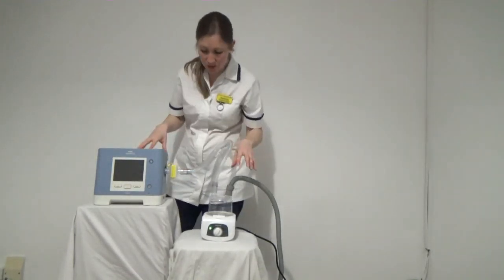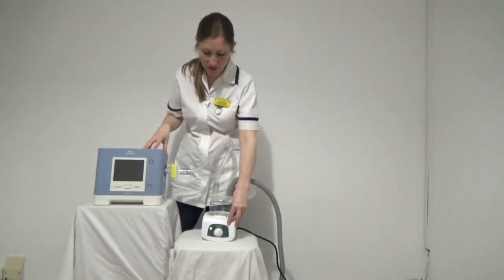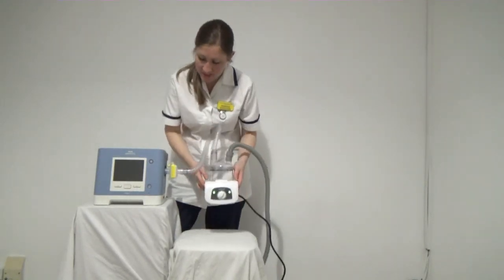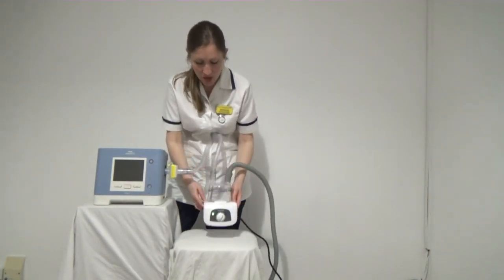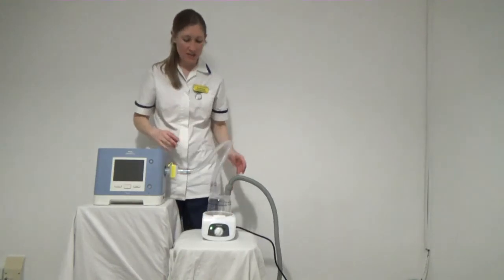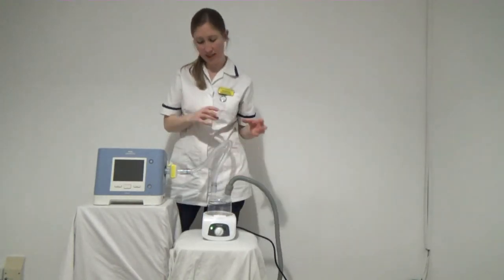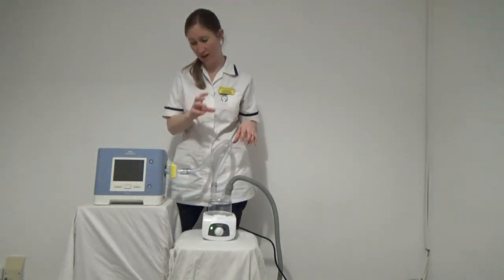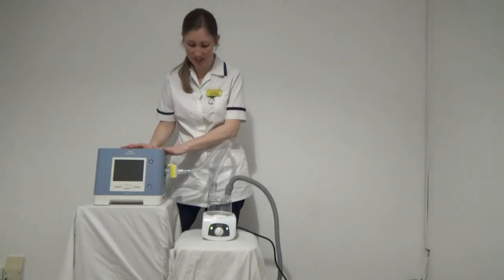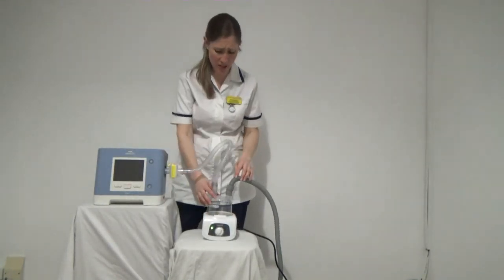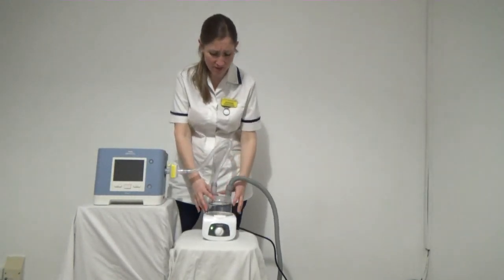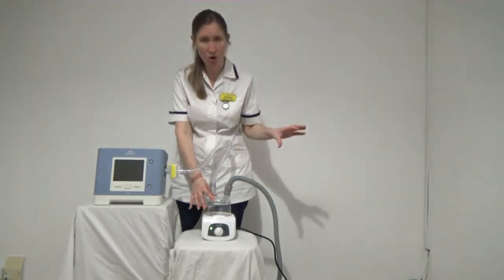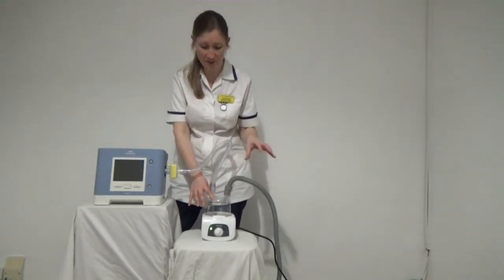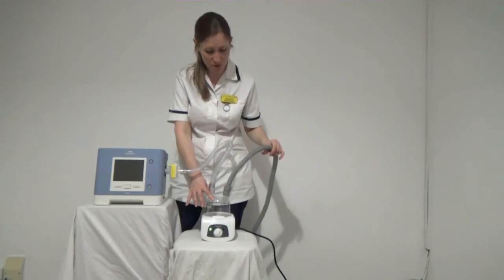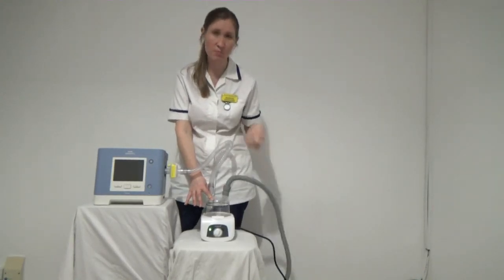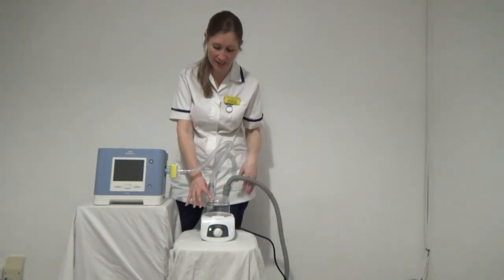It is important with the setup of the humidifier that the humidifier is either at the same level of the ventilator or slightly lower. This is to prevent condensation tracking from the humidifier back down into the ventilator. The same goes for the patient. You want the humidifier either at the same level or preferably slightly lower than the level of the patient's head, because we don't want condensation dripping from the tube down into the patient where it can collect in the mouth.